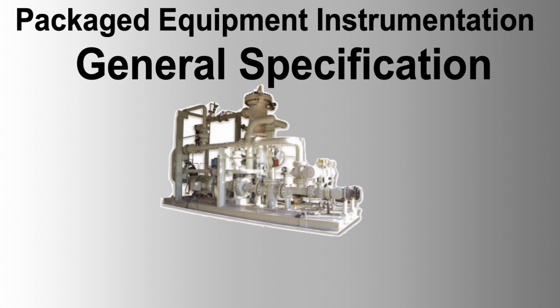Electronic instrument and instrument loop test. Electronic instruments and loops should be tested from the junction box to the instrument, ensuring cables have been Megger tested and that test equipment follows manufacturer recommendations. Relief valve test certificates. The vendor must issue test certificates for each valve fully compatible with API RP520 requirements.